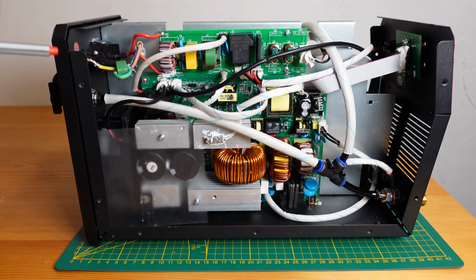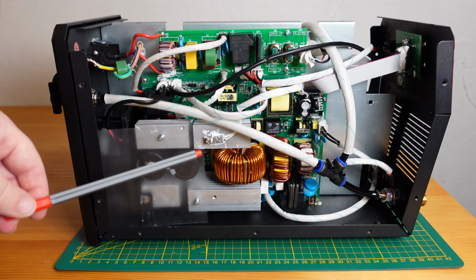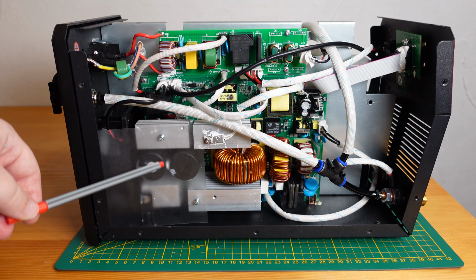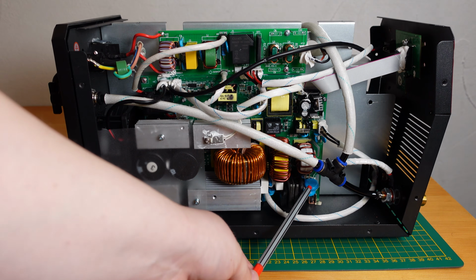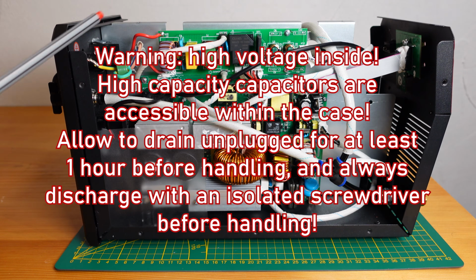So now that we are inside the case of the PPSK 40, here we have our main PCB that's doing all the voltage conversion. One quick warning first: here we have some large mains capacitors and also some high voltage capacitors. These will carry a charge if the device has been plugged in recently. So if you're going to be doing any maintenance inside here, make sure those are discharged.